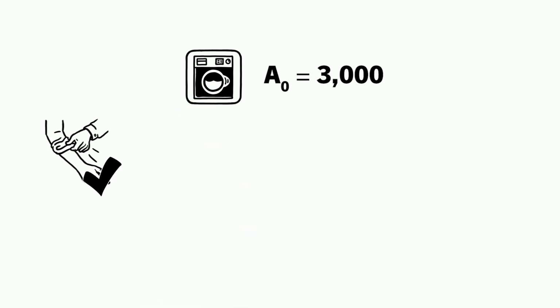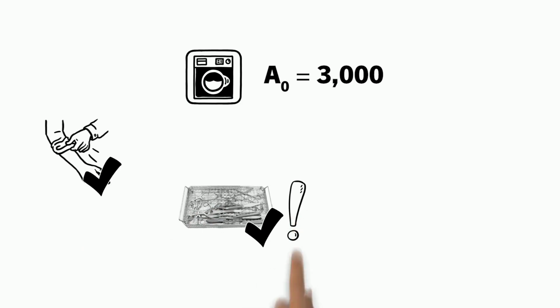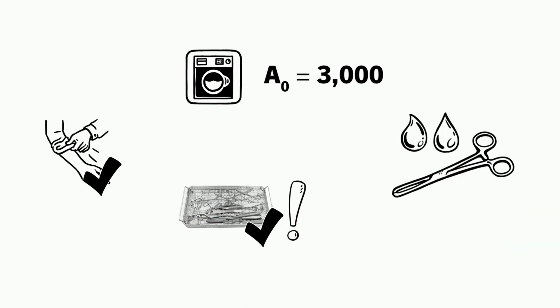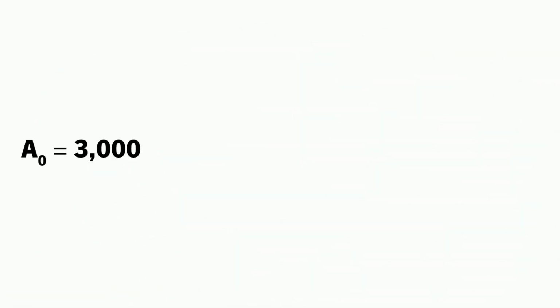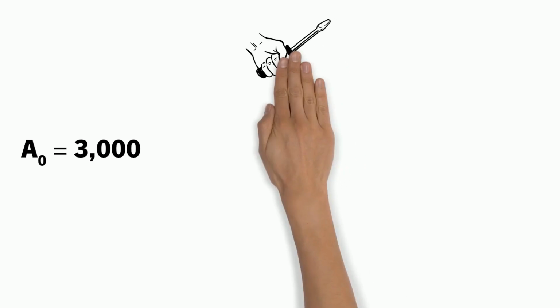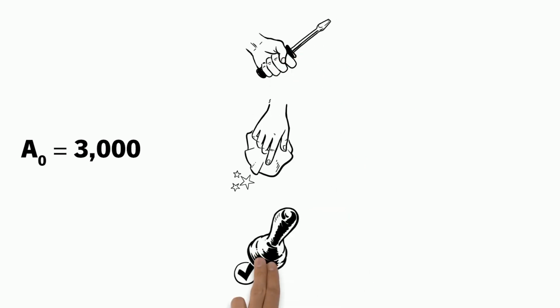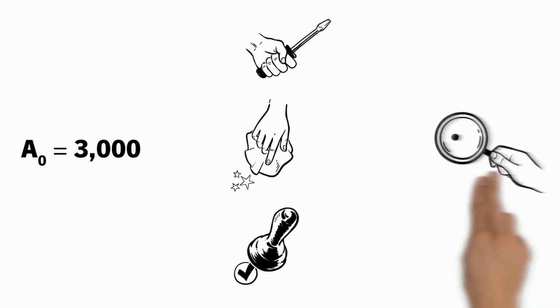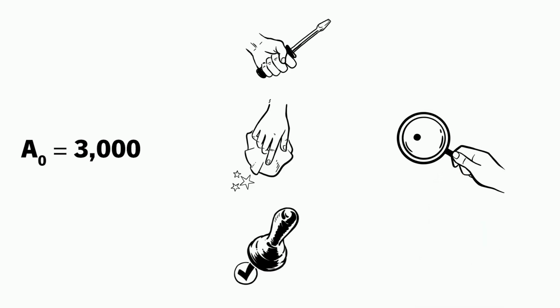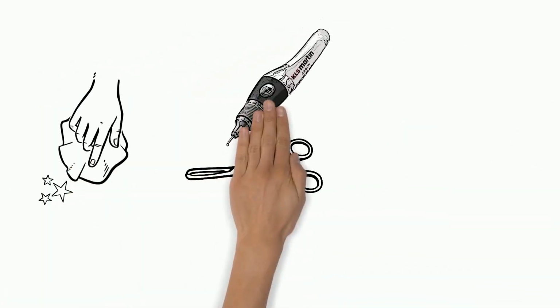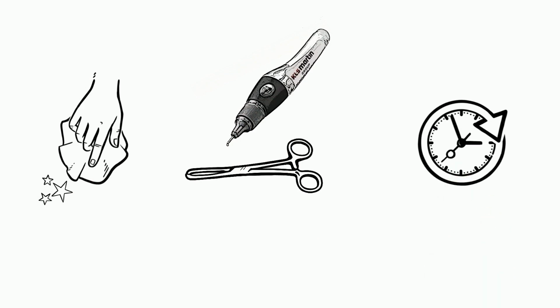Once the preparation is complete, the machine cleaning and disinfection follows. Particular attention must be paid here to the correct loading of the trays in order to ensure that the instruments can be rinsed sufficiently. After the instruments have been disinfected, they are reassembled, maintained and checked if necessary. Here the employee carries out a visual check for defects and surface changes. During maintenance, for example, instruments are oiled on moving parts in order to maintain their functionality in the long term.